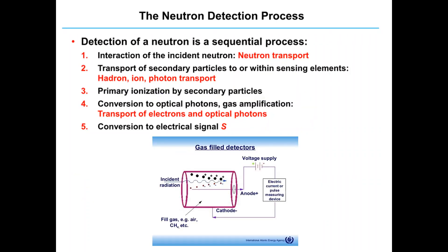The neutron detection process consists of five sequential steps. The first step is the interaction of the incident neutron — that is, neutron transport. We make the neutron interact with a particular kind of material. Those materials should have larger cross-sections for thermal neutrons and should have the capability of producing charged nuclei. In the second step, we carry out the transport of secondary particles — those particles produced due to the interactions of the neutron beam — within the sensing element.